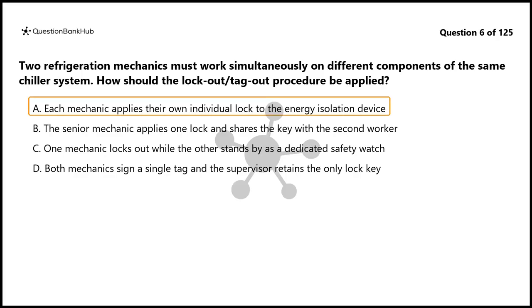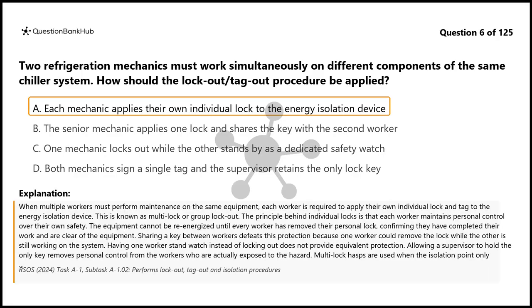The correct answer is A. When multiple workers must perform maintenance on the same equipment, each worker is required to apply their own individual lock and tag to the energy isolation device. This is known as multi-lock or group lockout. The principle behind individual locks is that each worker maintains personal control over their own safety. The equipment cannot be re-energized until every worker has removed their personal lock, confirming they have completed their work and are clear of the equipment.